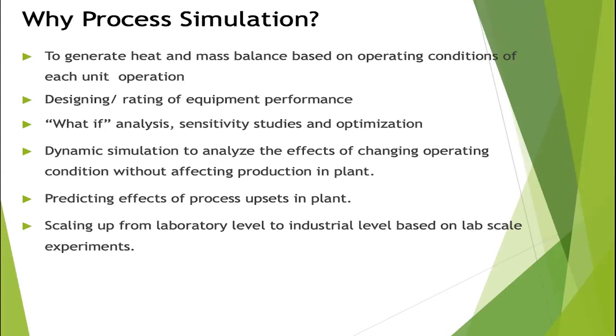Dynamic simulations are used to train plant operators by generating operator training simulators (OTS). You can perform what-if analysis — for example, increasing the operating pressure of a column and checking what happens to output purity. Simulation can also be used for scaling up: once a simulation matches laboratory results, the same parameters can be used to scale up to an industrial level.